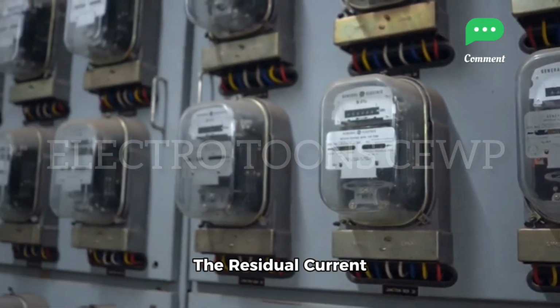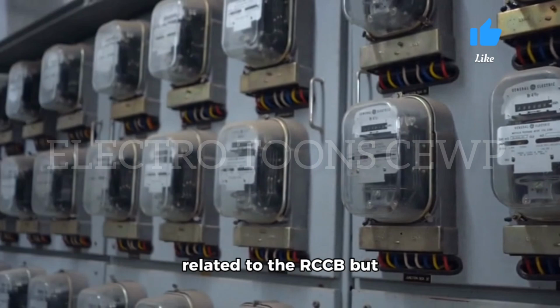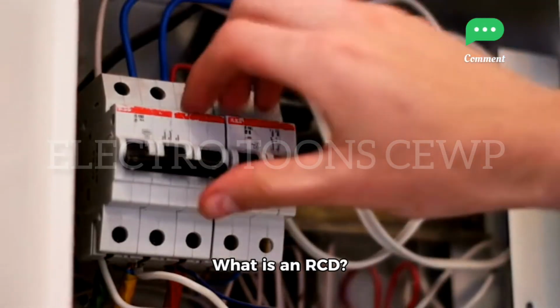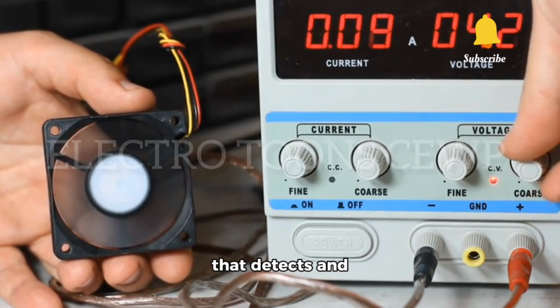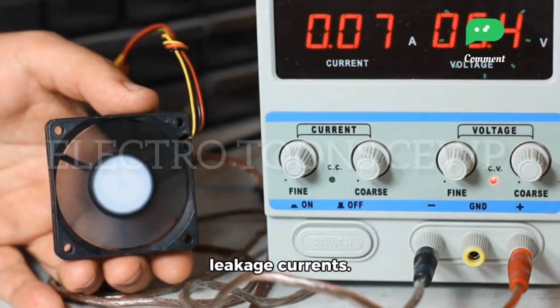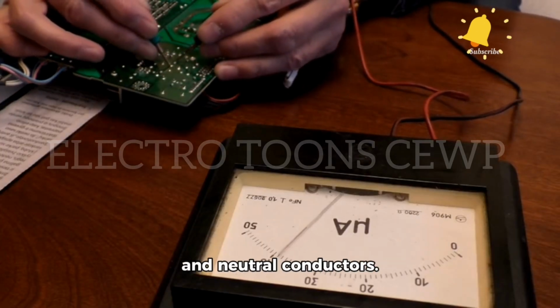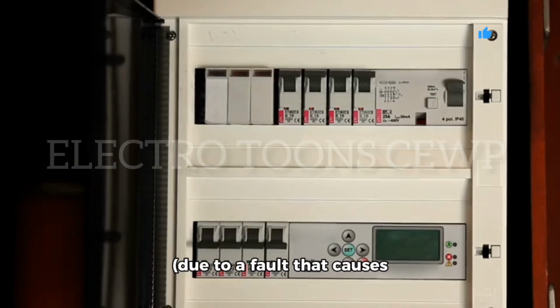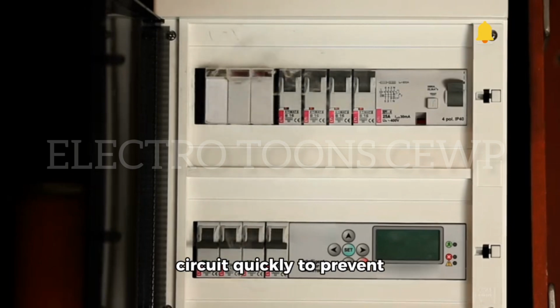RCD, residual current device. The residual current device, RCD, is closely related to the RCCB but has a slightly different function. What is an RCD? An RCD is a general term used for a device that detects and protects against earth leakage currents. It works by detecting any imbalance between the live and neutral conductors. How does an RCD work? When an imbalance occurs due to a fault that causes current to leak to earth, the RCD disconnects the circuit quickly to prevent electric shocks.